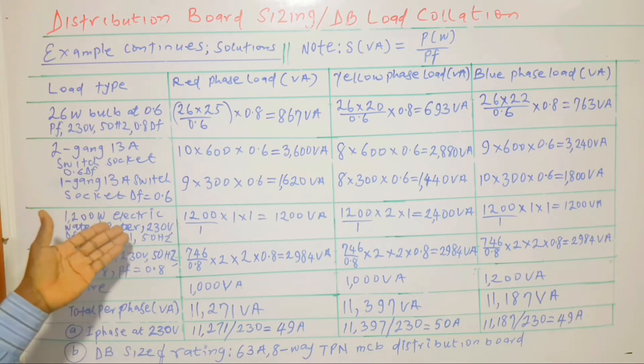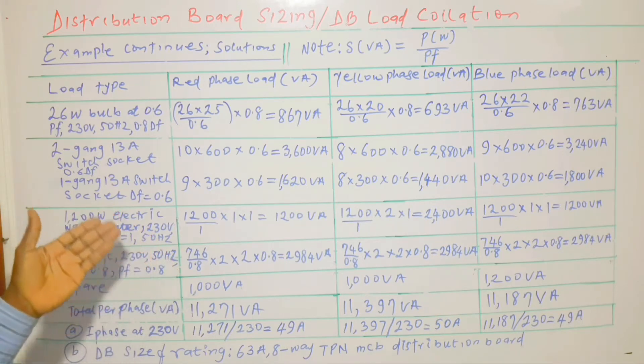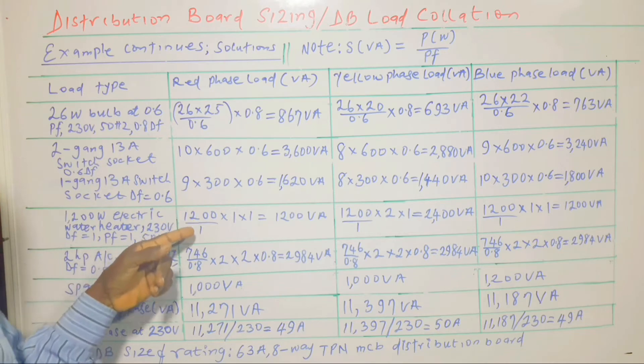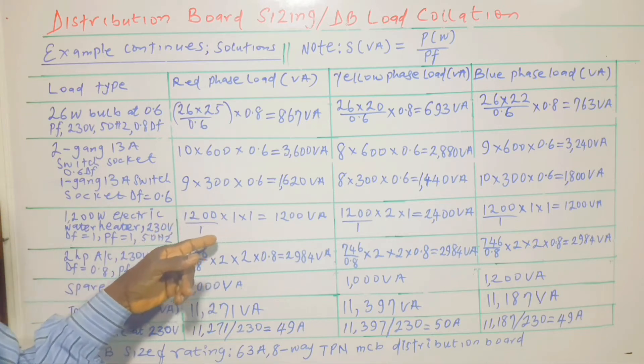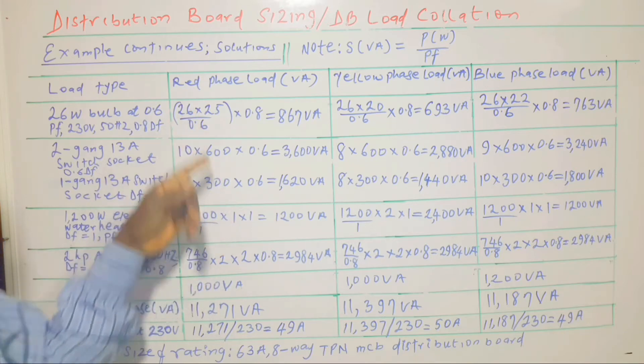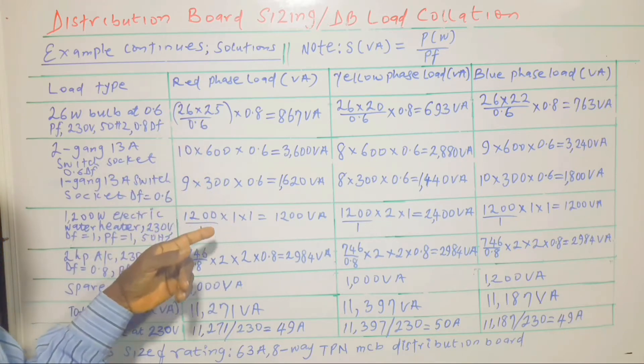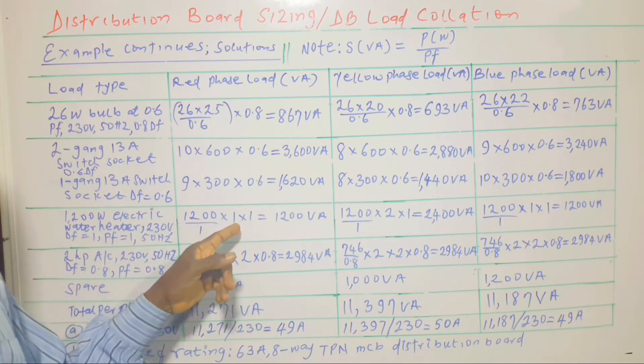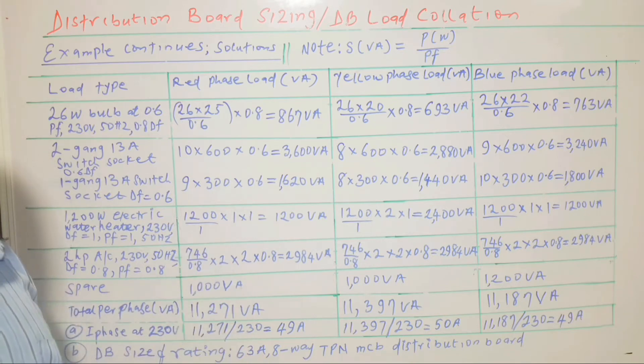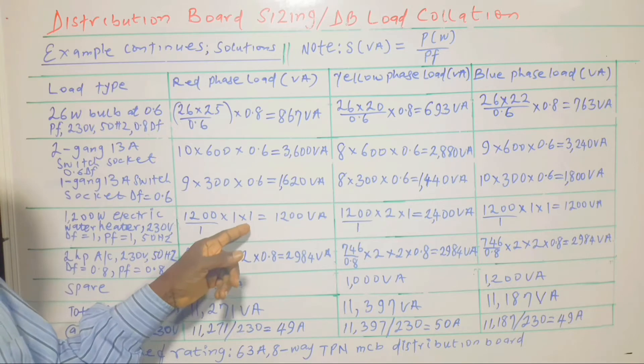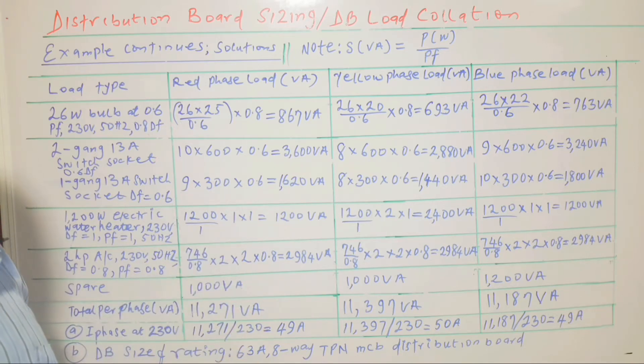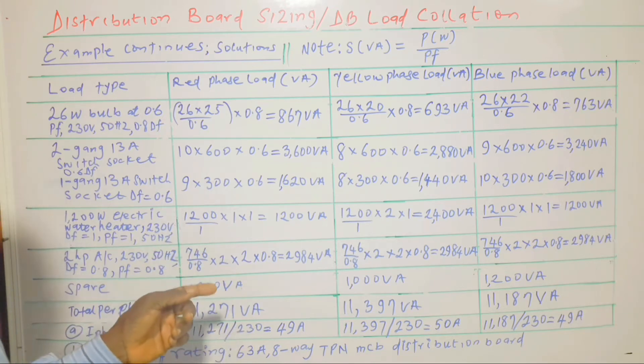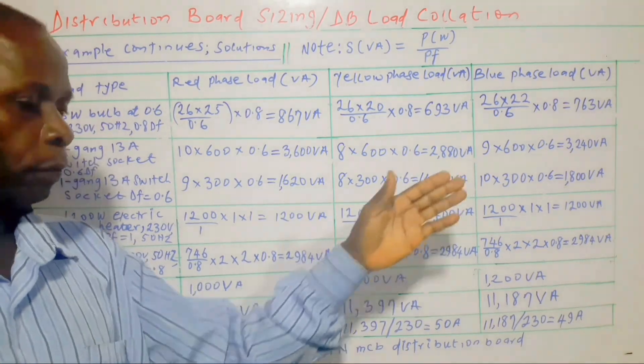For the electric water heater — a heating load — the power factor is 1, so the active power is divided by 1. We also multiply by 1 because there is only 1 water heater connected to the red phase, and the diversity factor is also 1. We don't apply a diversity factor when there aren't many of the same items. Similar calculations apply for the other phases.